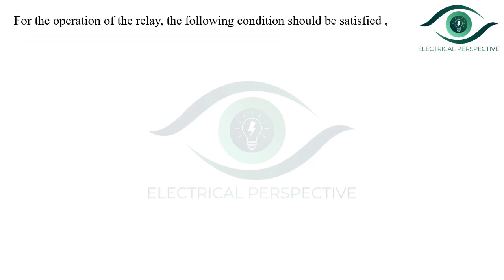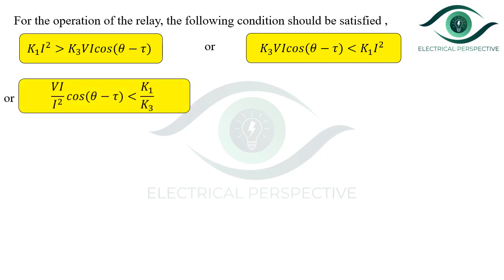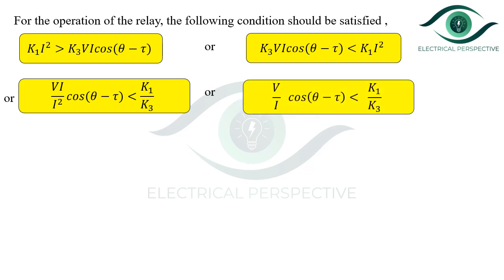For the operation of the relay, the operating torque must be greater than the restraining torque. The restraining torque is provided by K3·VI·cos(θ − τ) and the operating torque by K1·I². Simplifying, we get (V/I)·cos(θ − τ) < K1/K3, which gives Z_seen·cos(θ − τ) < K1/K3. Here V/I is the impedance seen by the relay, and K1/K3 is a constant equal to X_s, the preset value of reactance — the reach of the reactance relay.